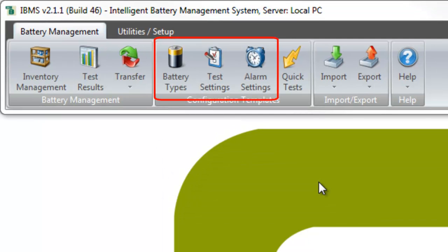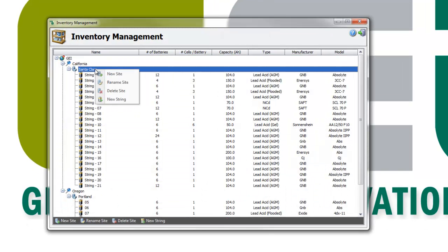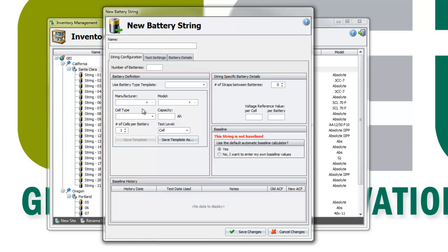These 3 templates can be modified anytime even if they are under use in the string configuration. This is because when you are using a template in the string configuration, the corresponding string configuration fields are filled up according to the template information, and the corresponding string configuration and template are not further associated. You can modify these fields when setting a string configuration without affecting the original template. You can save those modifications directly into this template or into a new template.